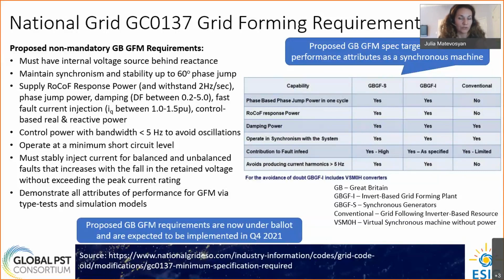There is no requirement to oversize inverters. It's just that the provider of the service would need to inform what the peak current rating is, and then it should comply with the other requirements within its rating, and not go beyond it. So there is no requirement to oversize. And then there are extensive descriptions about how tests and simulations will be done to verify these capabilities.